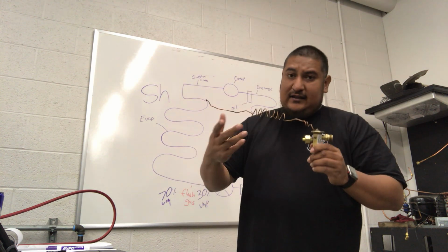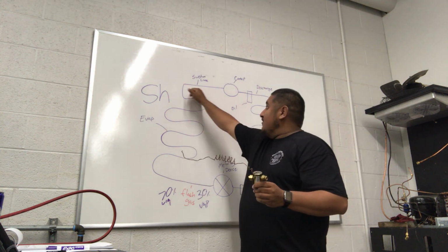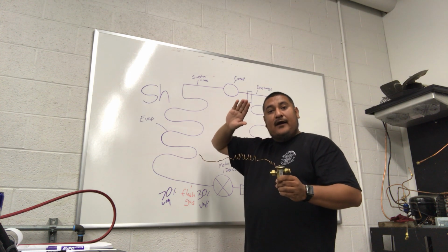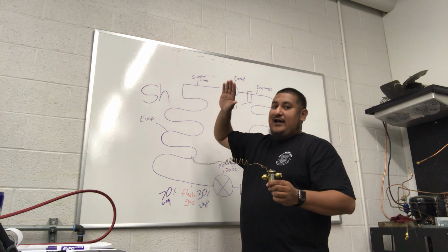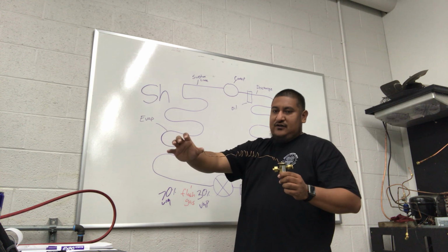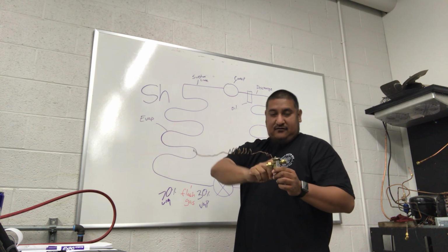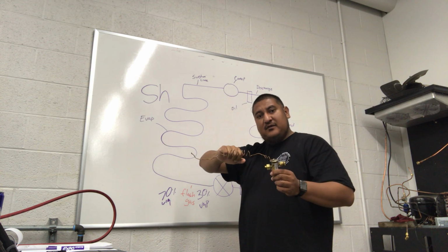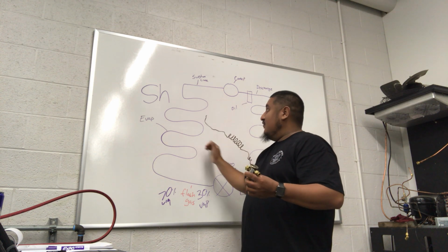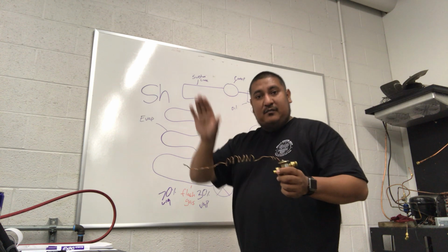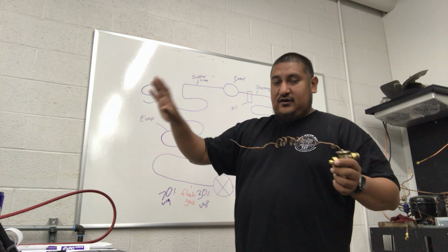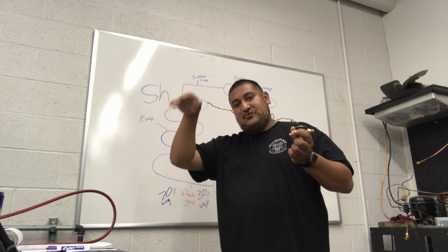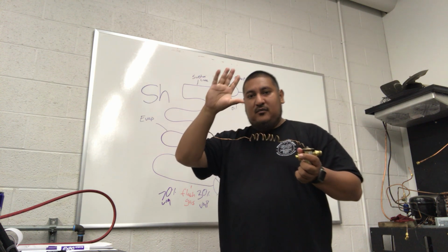Once you close the valve, you're going to reduce the amount of liquid that's going into this guy. And then what's going to happen? Well, this suction line temperature will start to go up now, right? Oh, it's getting a little too hot. Pressure's going to increase here. It's going to push on its diaphragm. It's going to start to open up that valve, and you're going to start to send more liquid. So this guy here will basically do this. If you have a trend of this guy, you'll see it opening and closing, opening and closing.